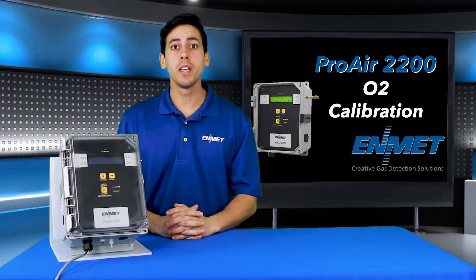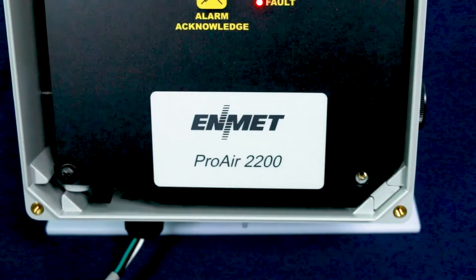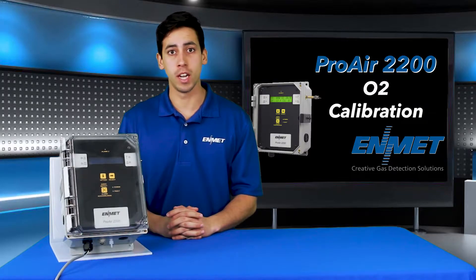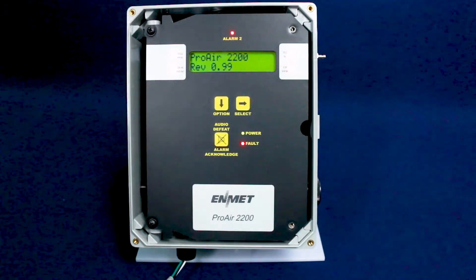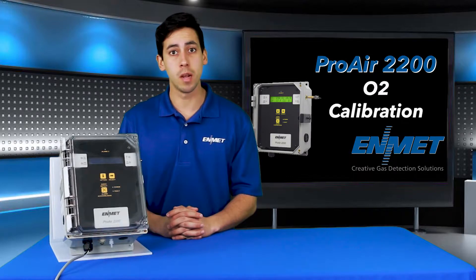In this video I'll be walking you through how to perform a calibration procedure for the O2 channel of ENMET's Proair 2200 compressed air line monitor. Before starting a calibration for the O2 channel you must supply air and power to the Proair for at least a 15-minute warm-up period to allow the sensor to stabilize.